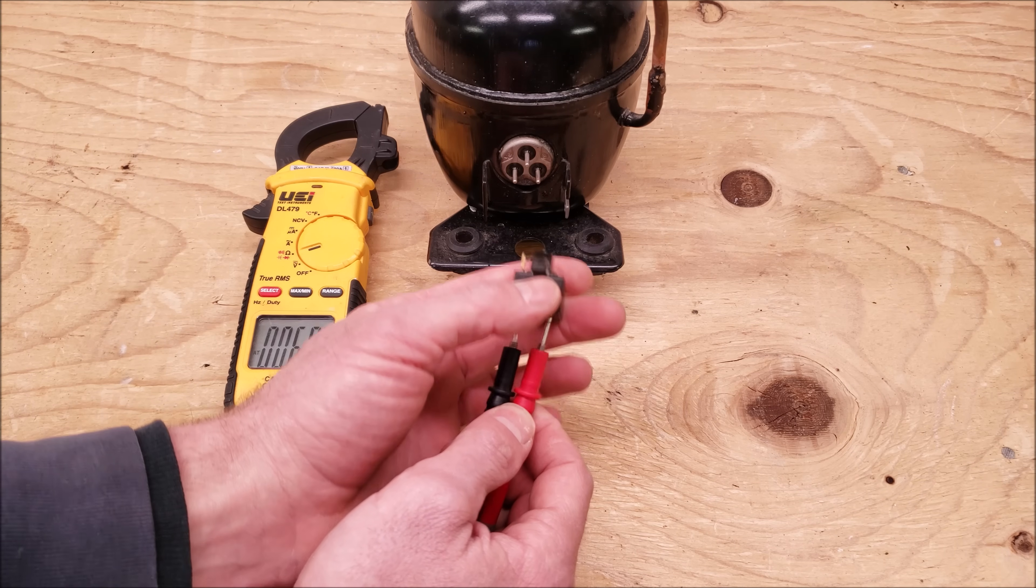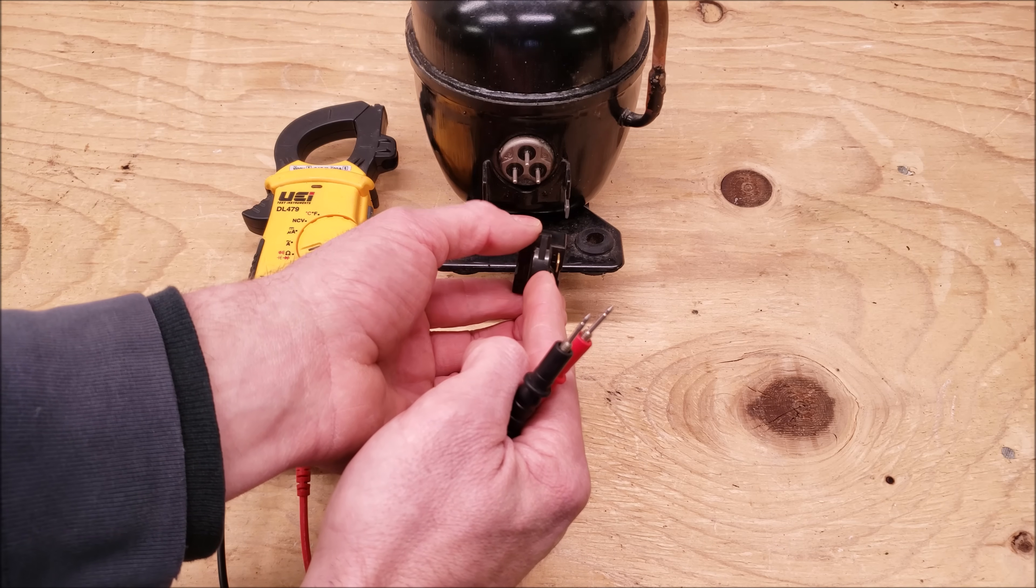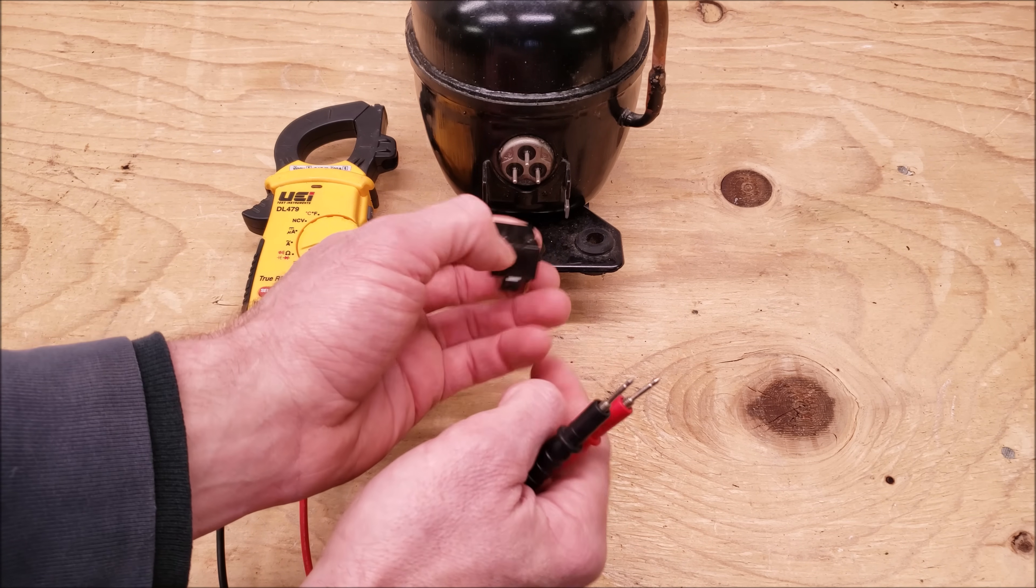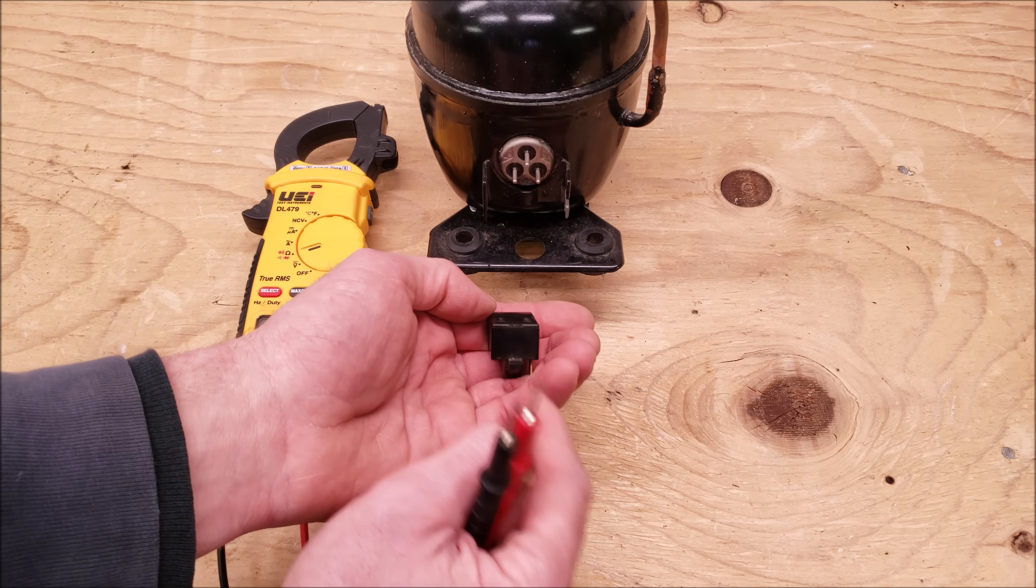So what's going to happen is when this starts up it's going to end up heating up the PTC thermistor and it's going to kick the circuit out. So the start winding and the run winding inside here are no longer connected.